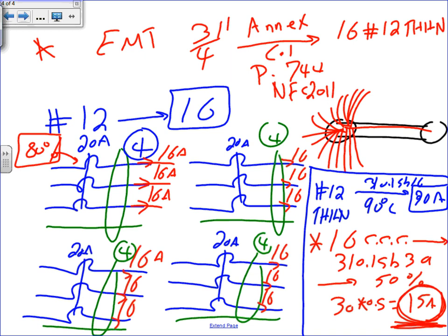See why I went through the whole running around to get you to the 15 amps. Now, Rob, does it make sense to group in this case? If I'm only losing 1 amp in a 20 amp circuit, yeah. If I'm losing 5 amps, no. Now take this. You see why I chose 3/4 inch? Take an inch and fill that baby with God knows how many number 12 conductors, and do the derating, you might lose 4 amps. Now, 4 or 5 amps on a 16 amp circuit is a substantial amount. It doesn't make sense to group them. You can, but it's not a good idea.